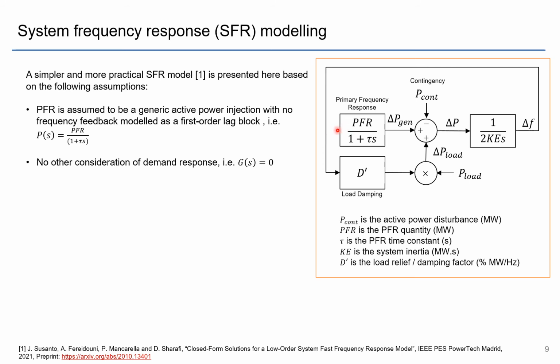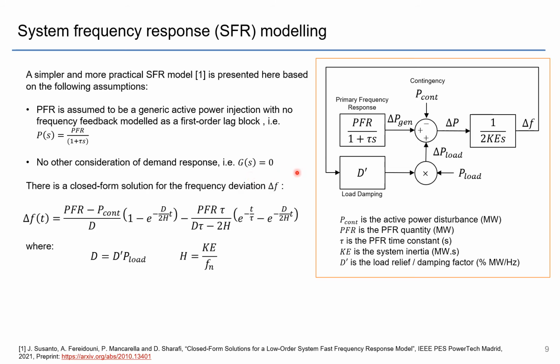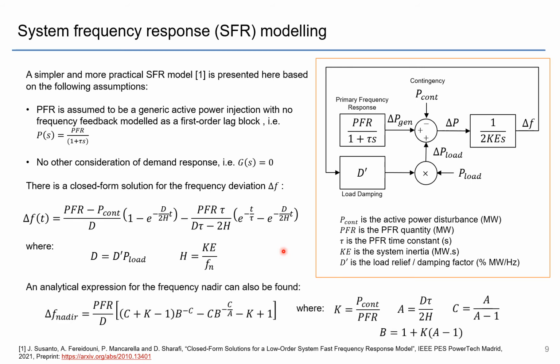And what we're saying in this is it's just modeled as a first order lag block, so you have some quantity of PFR, and then you have a speed of response of that PFR. And this is a useful formulation when we want to provision the amount of spinning reserve or PFR required in any given situation. And there's also no other consideration of demand response here, so GS, the transfer function, is 0. Like the Anderson model, this one has a closed form solution for the frequency deviation, and here is that formulation. And another more attractive feature as well is that it has an analytical closed form solution for the frequency nadir. So you can calculate the frequency nadir without having to calculate the frequency deviation, then taking the minimum of it.